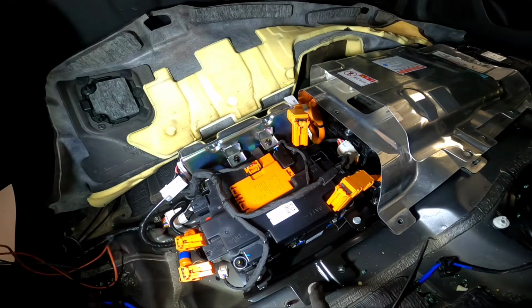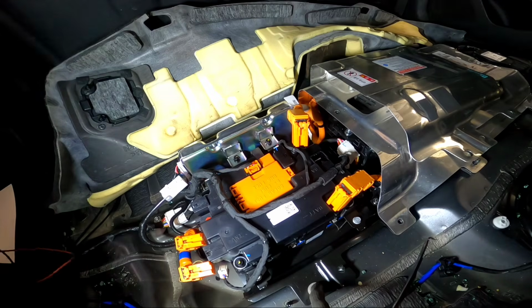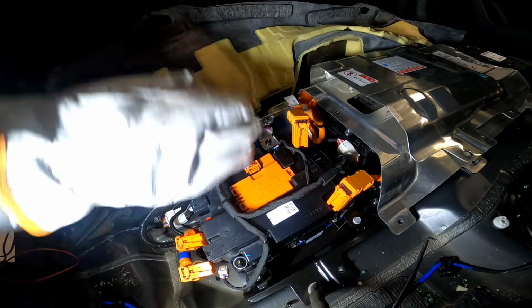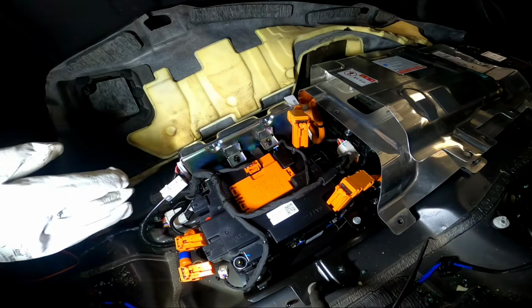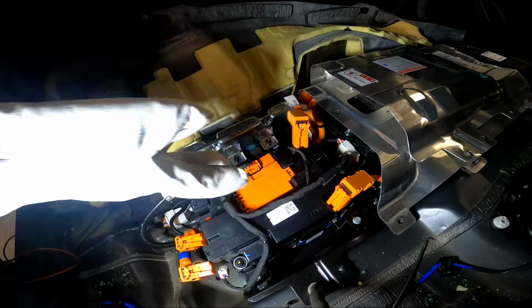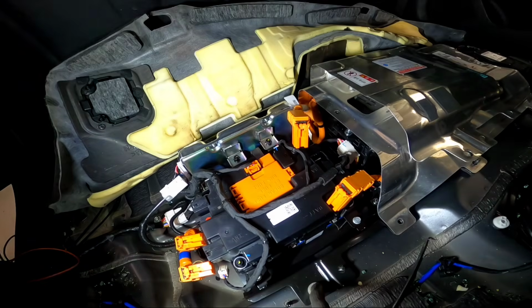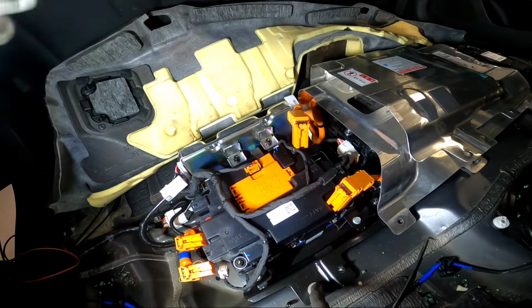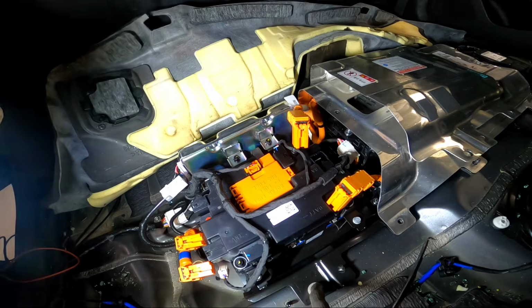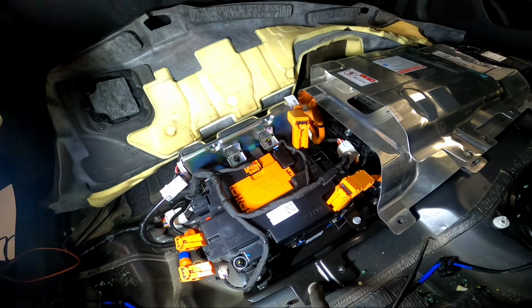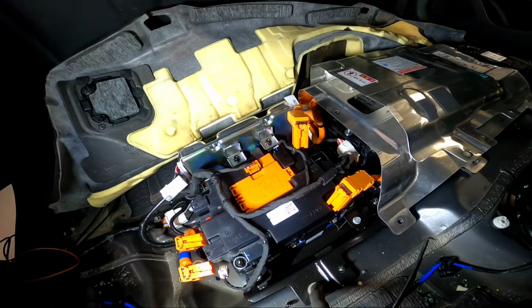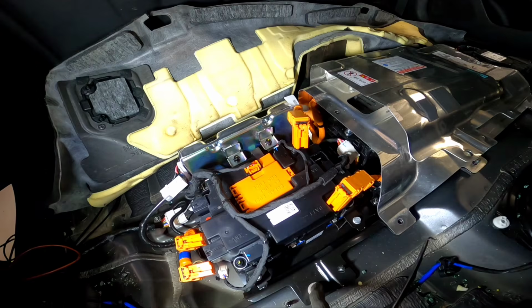But the question is, earlier when we tried to shut it off, we still had voltage in the front, and there should be no voltage there because we're not commanding the PRA to turn it on. We shut off the whole thing, right? So the way that shows, it means our relay there, the switch side, is stuck closed, most likely the positive side, because we didn't hear that click. The negative side, we hear that click, and we saw on our scope that it's switching up and down. The coil side is okay, right?